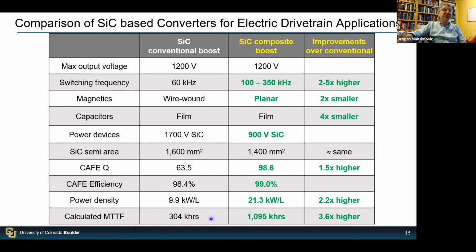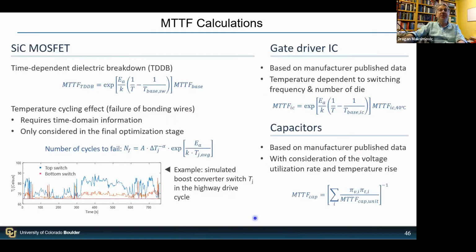I have to admit this is calculation based, but it's not completely empty. The calculated mean time to failure for the conventional boost with silicon carbide, done in a straightforward manner, is actually 3 times lower than the calculated MTTF for our system—even though we have a larger number of devices, those devices are stressed less. The calculation of the MTTF follows standard industry practices.